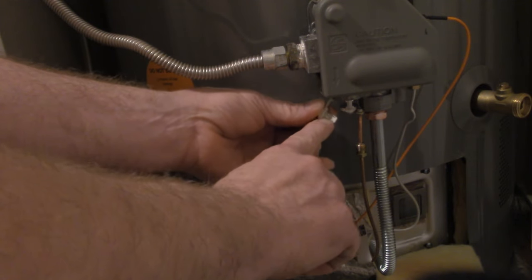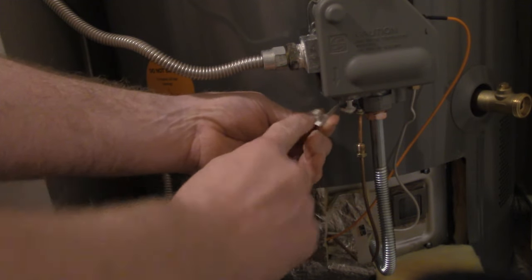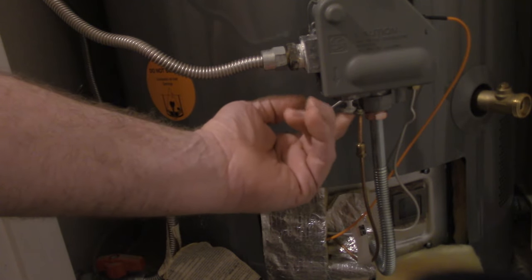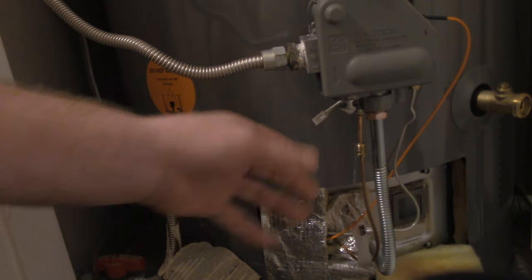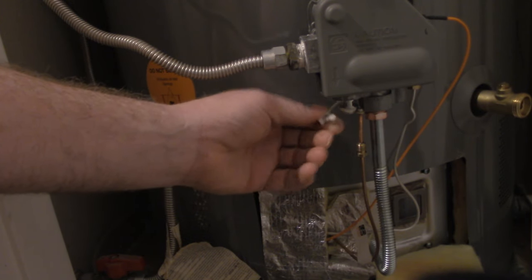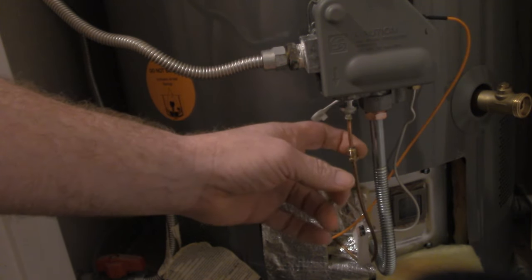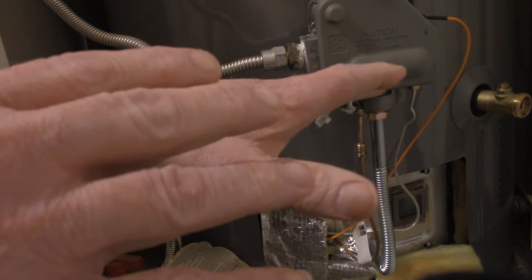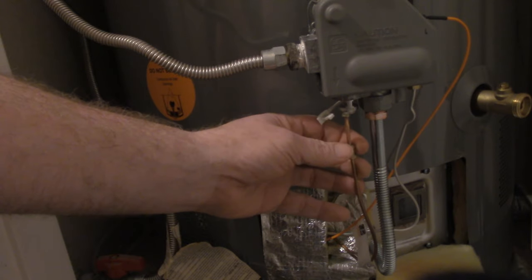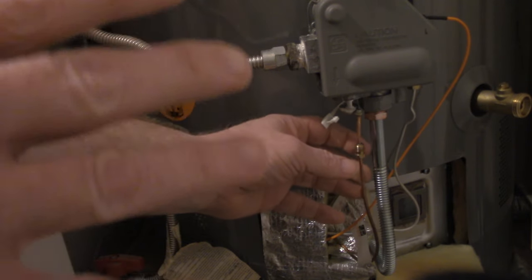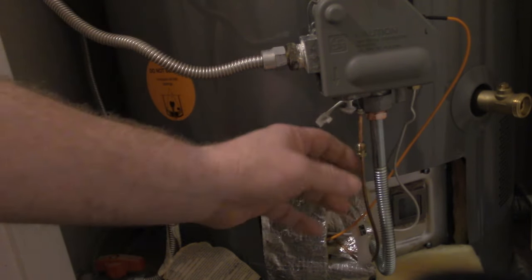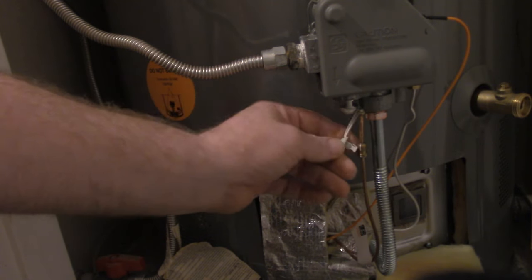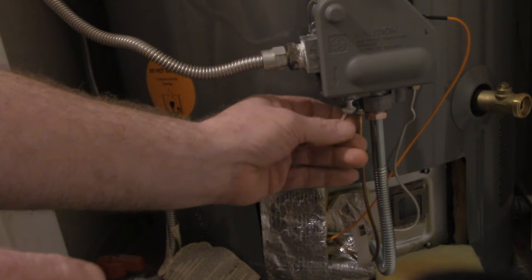It's got two wires that both go into that emergency cutoff. There is a small wafer on each side that actually sets between the thermocouple and the coupling. What happens is this goes bad and when that goes bad it breaks the electrical connection between your thermocouple and your solenoid. So these thermocouples don't go bad or I'm sure they do go bad but they don't go bad. That's not the primary problem with that. It is this emergency cutoff.